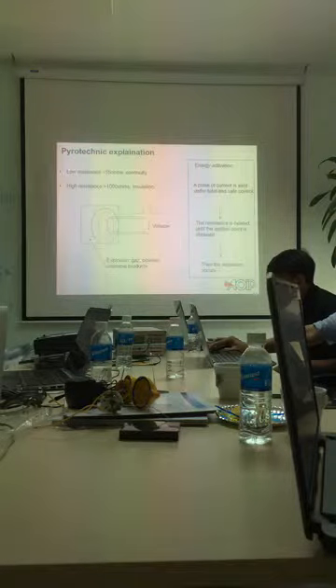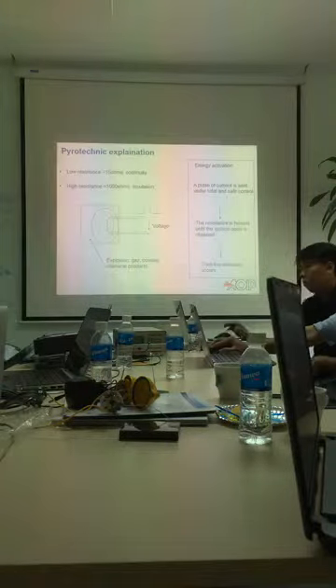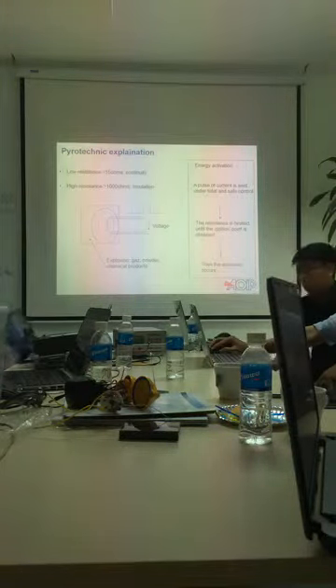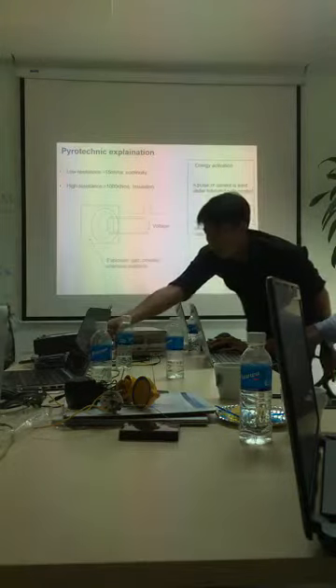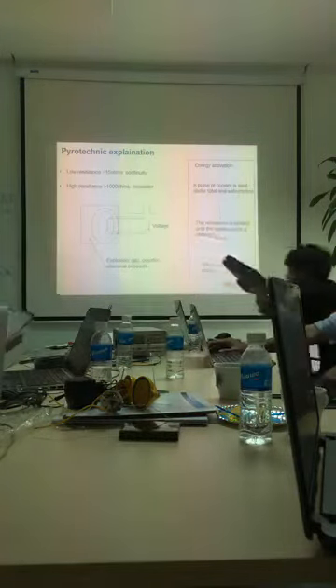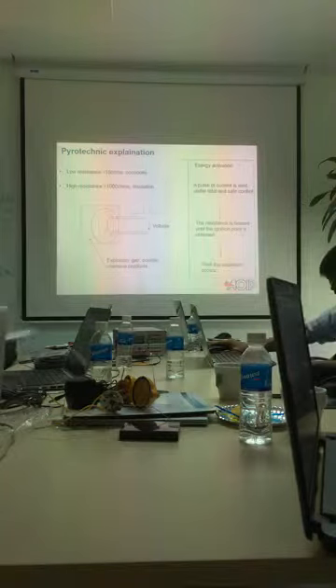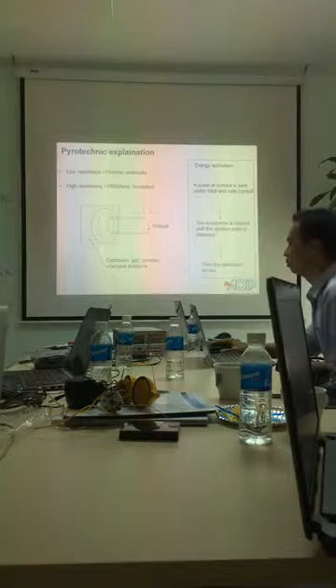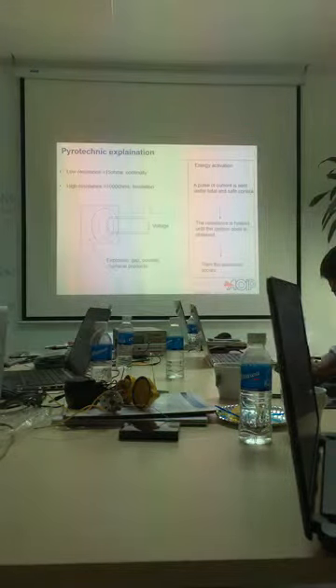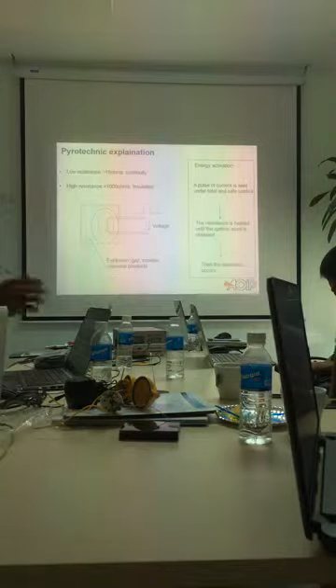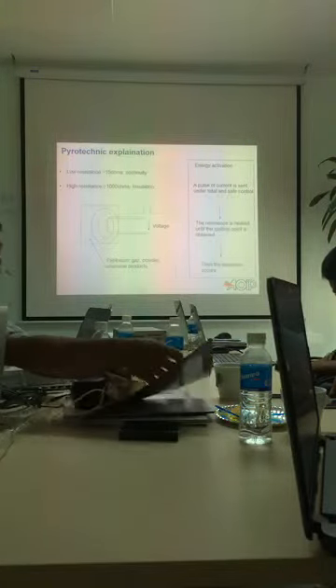It's a small box, and we will use resistance. It's resistance measurement. The resistance inside the explosive device will allow us to know if the product is functional or not. The principle is just as it is written, benchtop ohm meters. So it's resistance measurement.